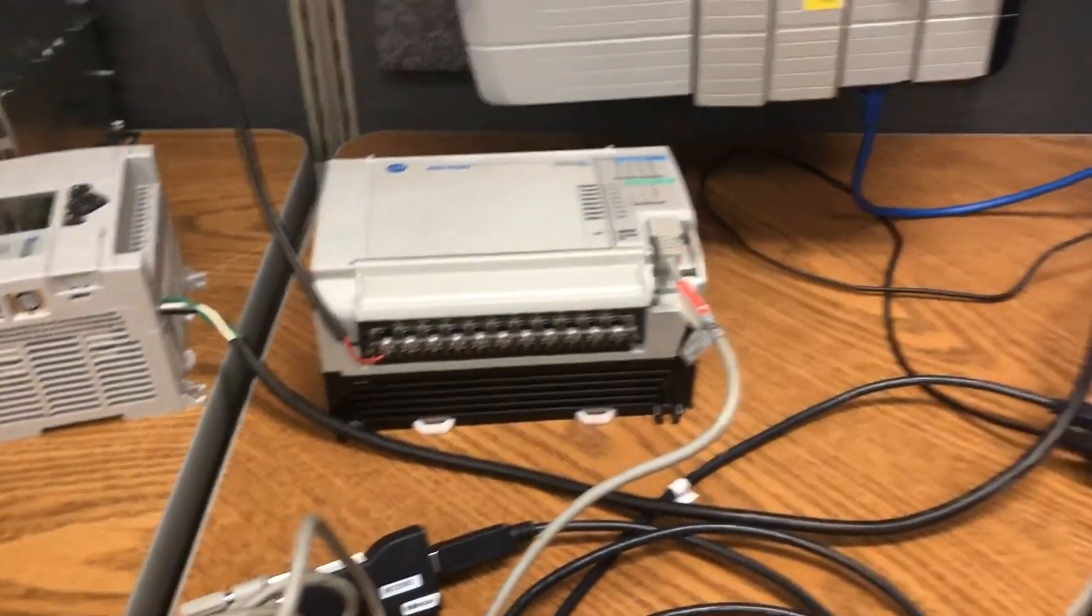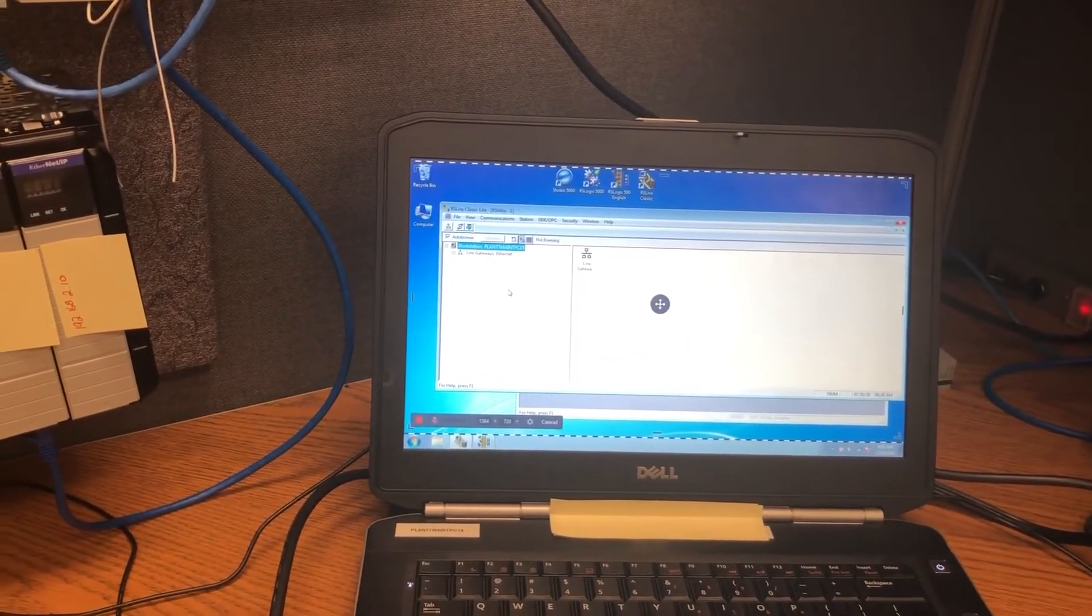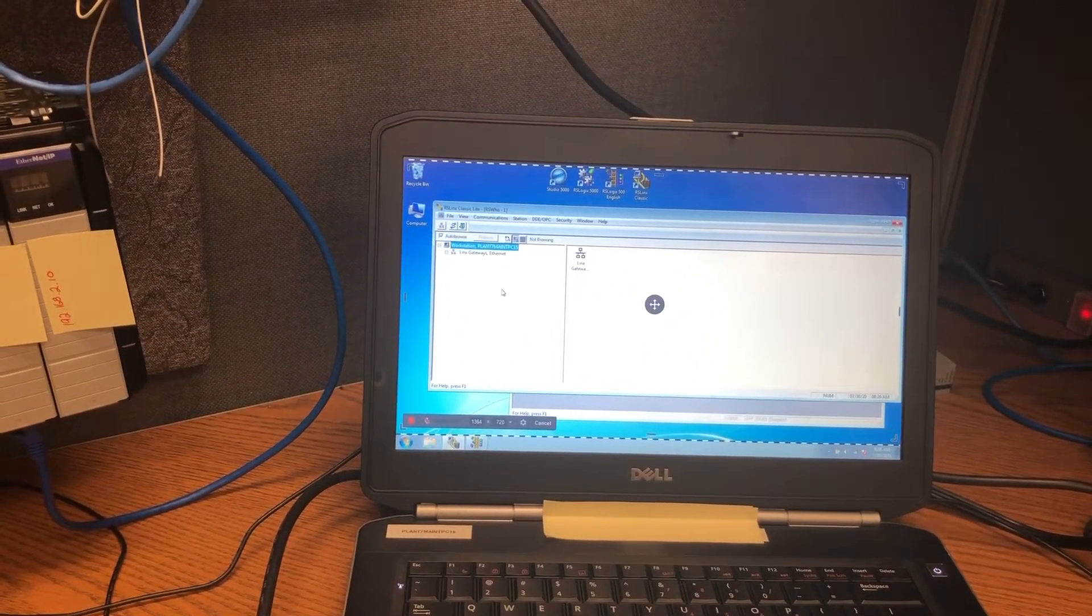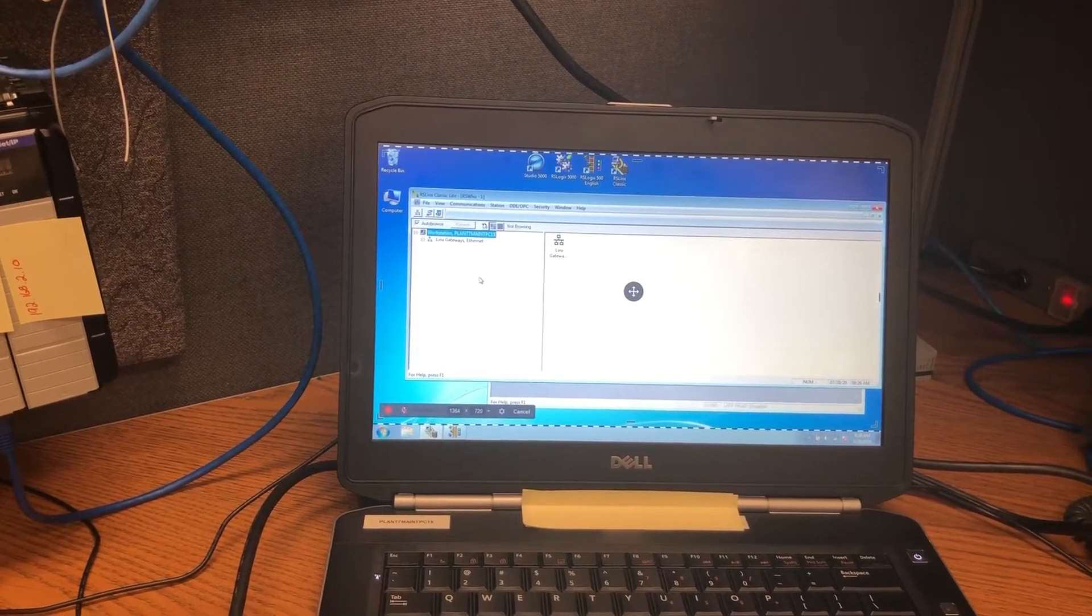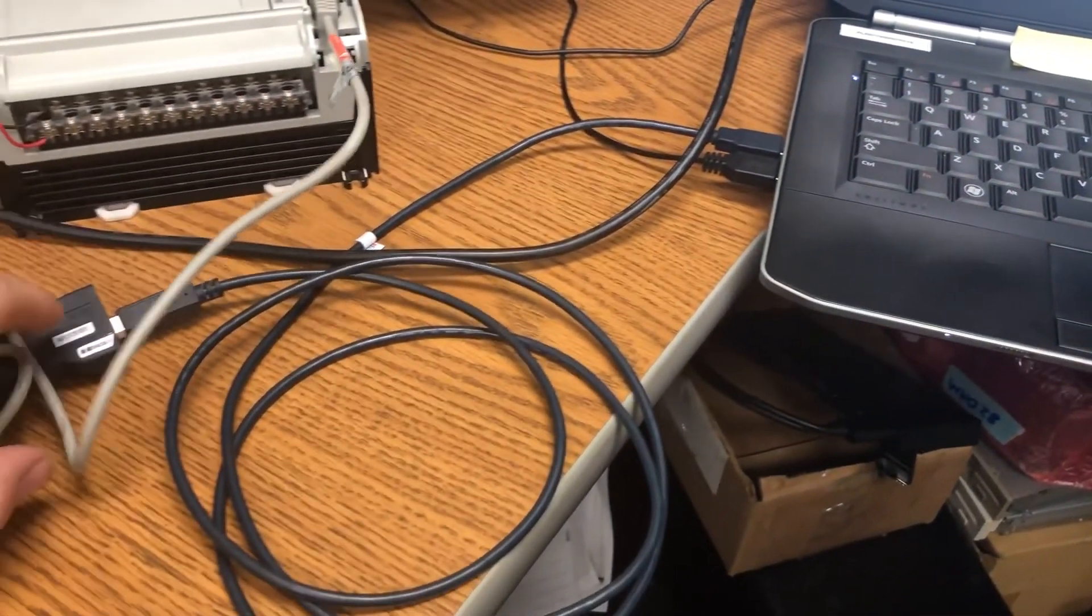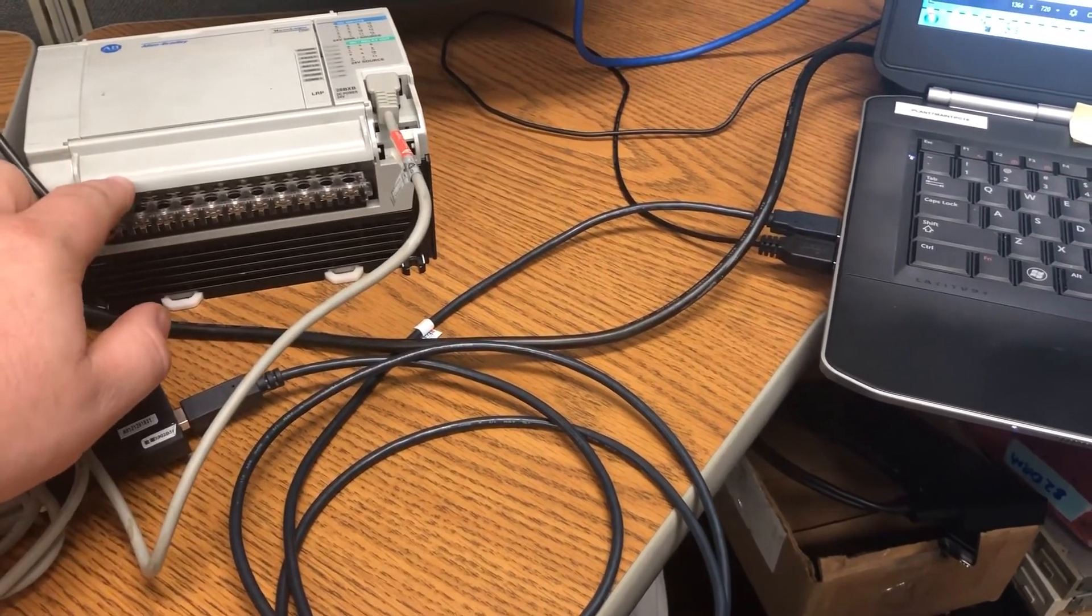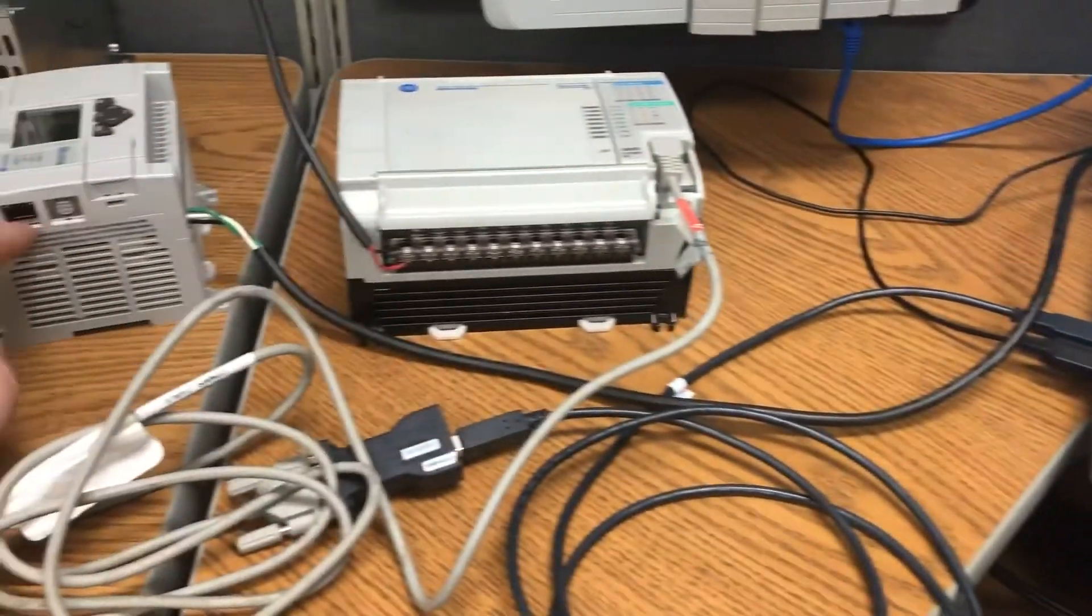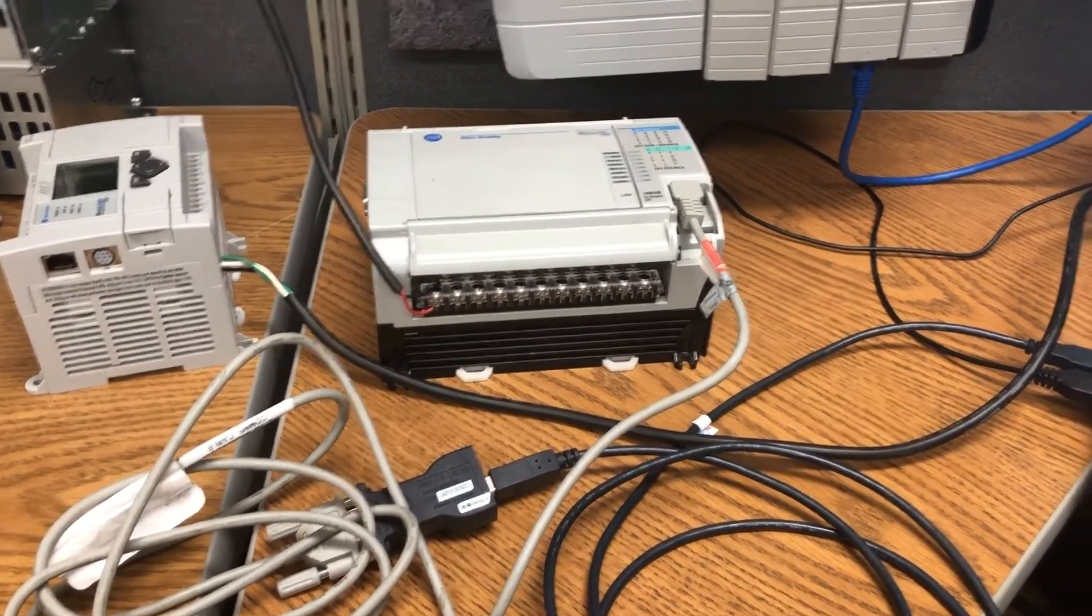I'm going to use some screen capture software, as you can see I'm set up for it, and I will be walking you through setting up the serial DF1 driver and then going in and selecting my COM port, which right now is set up on COM 3. You're going to see me set COM 3, set Micro Logix type, auto-configure, then I'm going to move this to this one and auto-configure again. So you'll see all that in the screen capture.